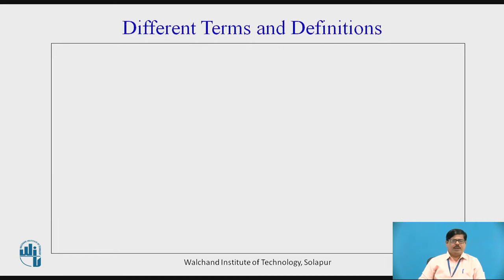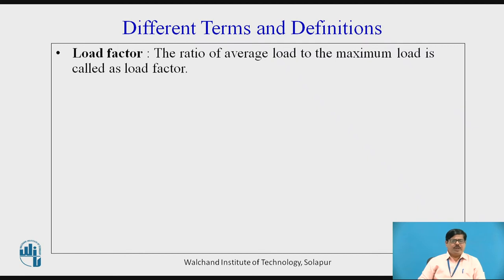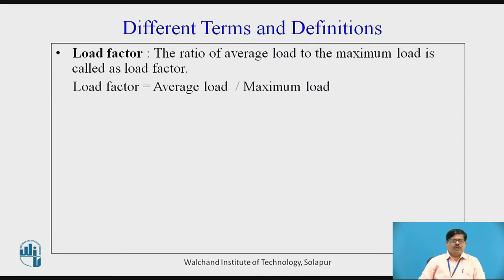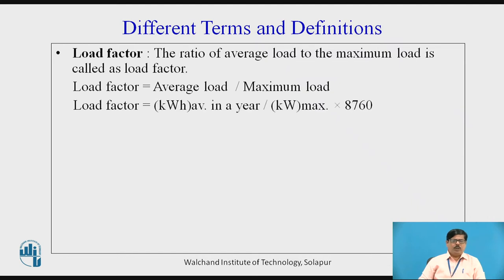The next very important term related to power plant performance is the load factor. It is defined as the ratio of average load to the maximum load. The load factor is required to be high — if its value is close to 1 or 100%, the power plant is being utilized economically. A lower value of load factor indicates that the power plant is being under-utilized.